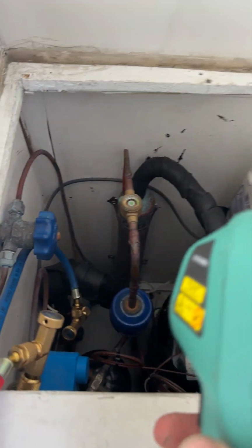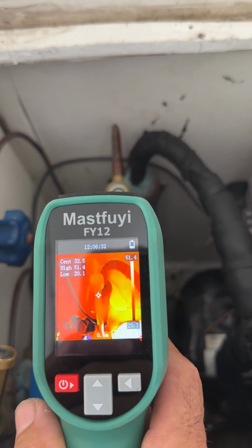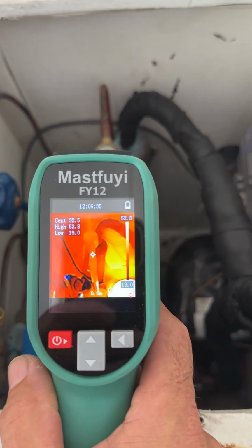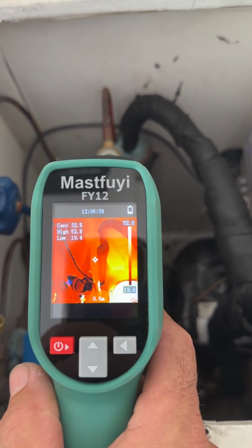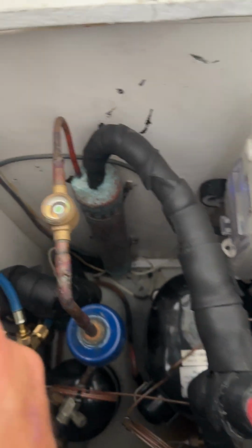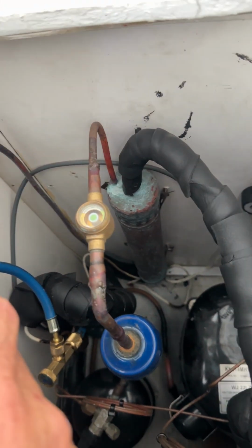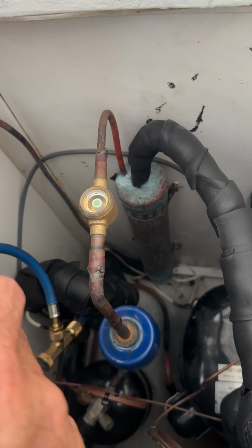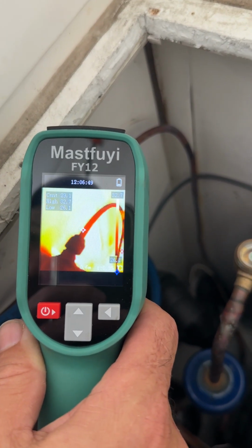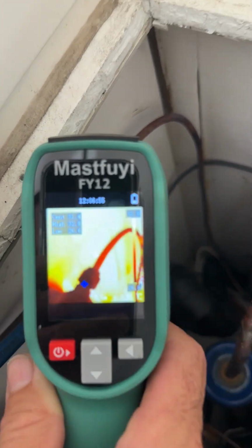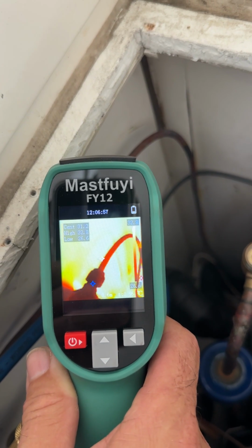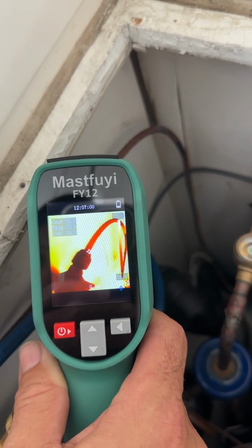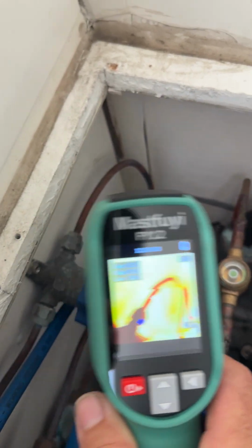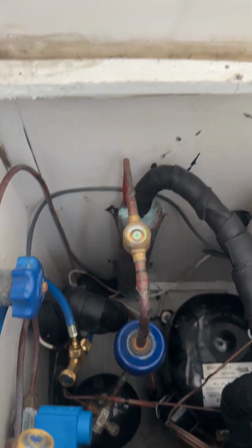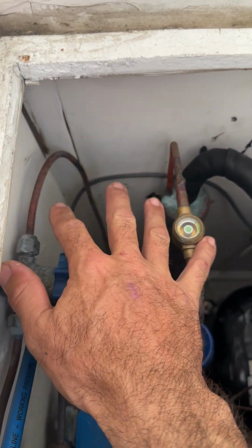So an example of this is on this temp gun. You can see there it's showing about 32.5 degrees on the pipe right in the centre. And then after the liquid suction heat exchanger, it's showing, sorry, let's get the focus. Look there, it's showing about 27.7. So it's reducing the heat between this side and this side by about 5 degrees.